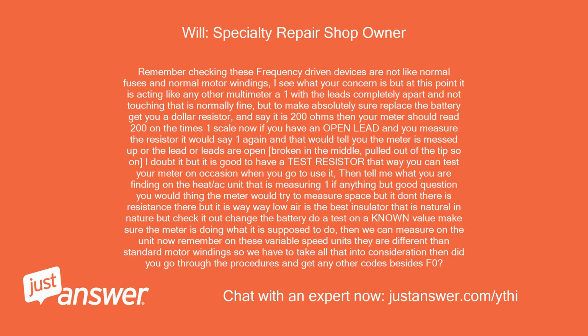Remember, checking these frequency-driven devices is not like checking normal fuses and normal motor windings. I see what your concern is, but at this point it is acting like any other multimeter, a 1 with the leads completely apart and not touching. That is normally fine. But to make absolutely sure, replace the battery, get a $1 resistor, and say it is 200 ohms, then your meter should read 200 on the ×1 scale.